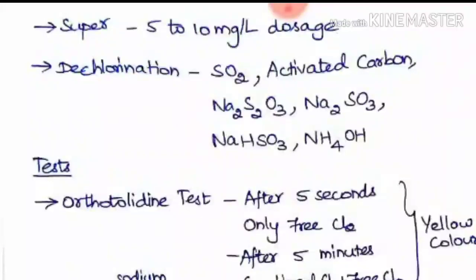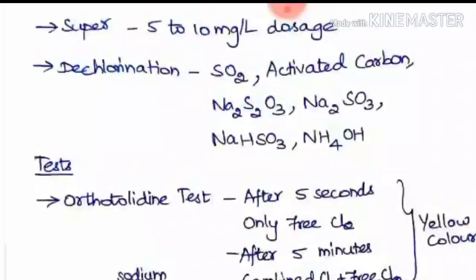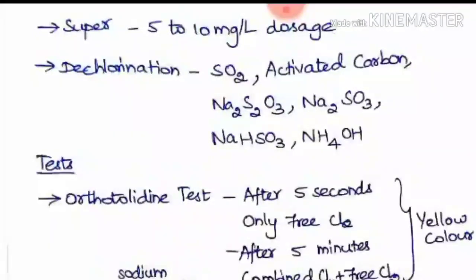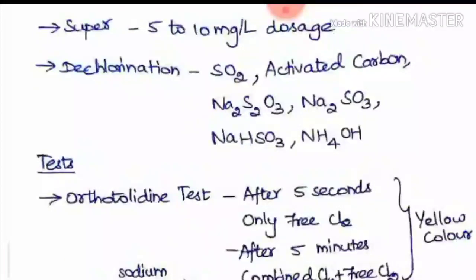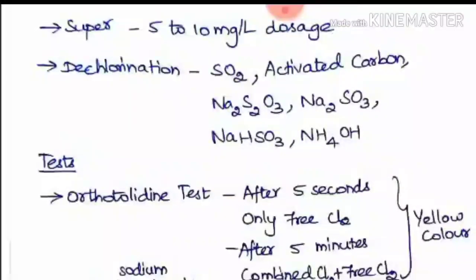There are various tests for finding the intensity of chlorine present in water. The commonly used test is the orthotolidine test. The orthotolidine reagent is added to the water and after 5 seconds a yellow color blooms, giving the free chlorine intensity. This is compared with a standard solution to find the amount of free chlorine. After 5 minutes the color intensity increases, giving the combined chlorine plus free chlorine reading.